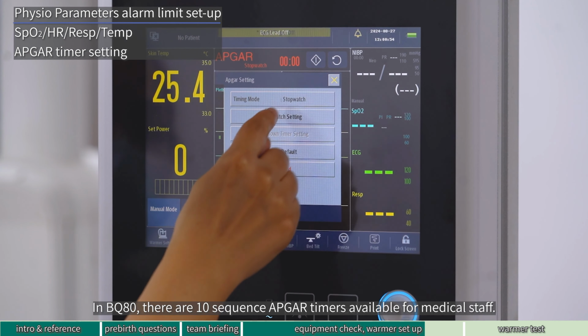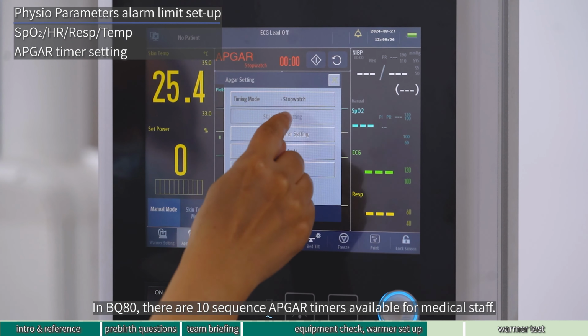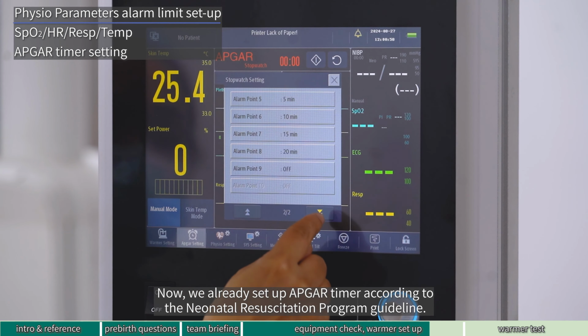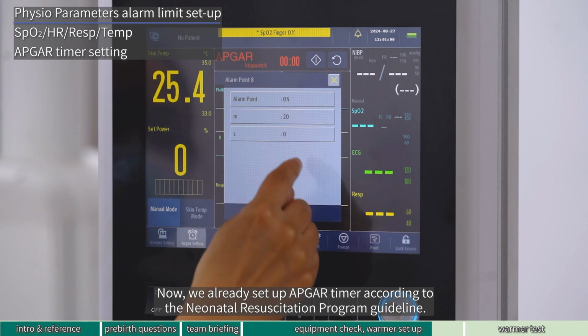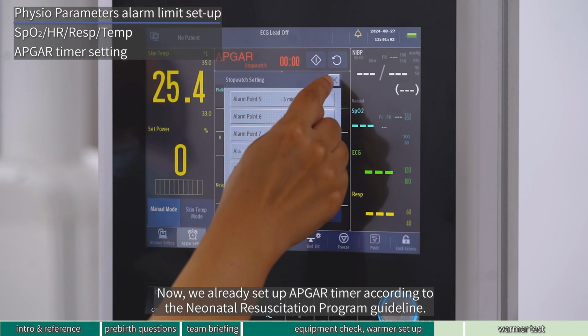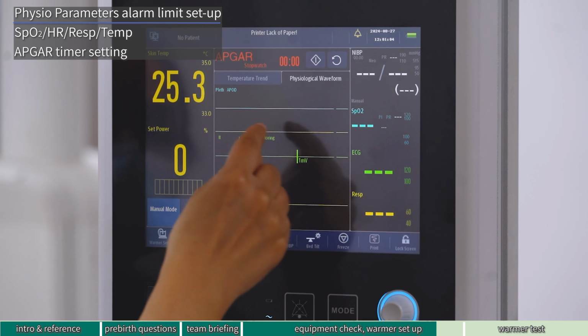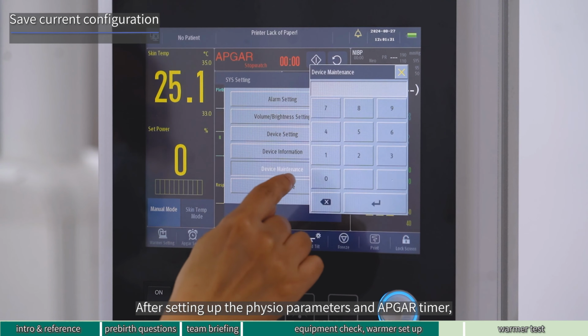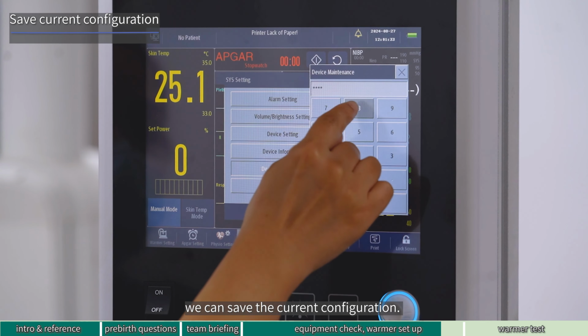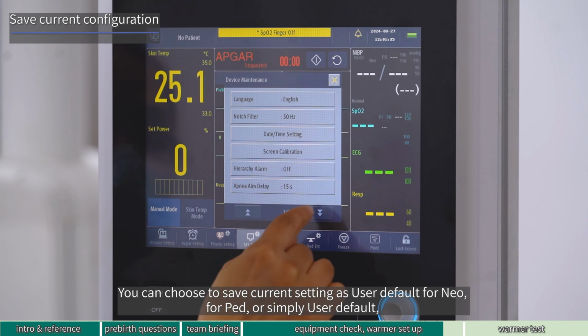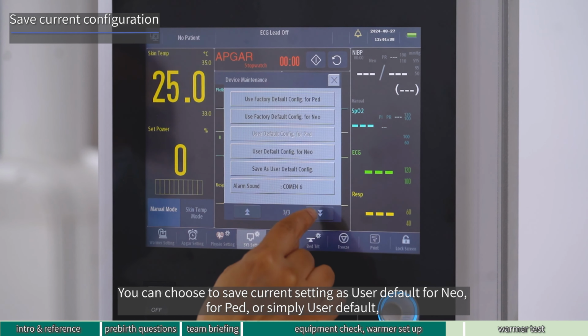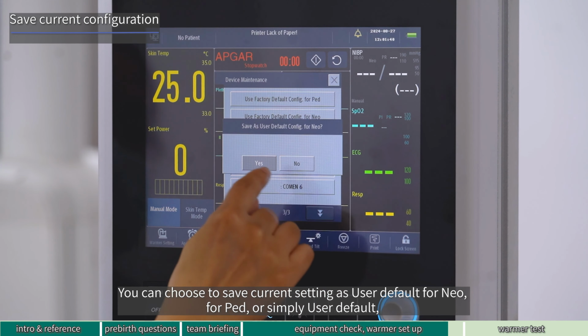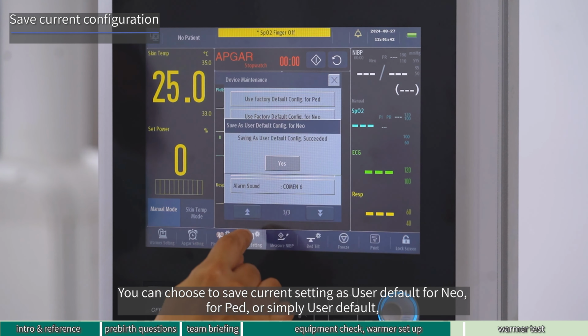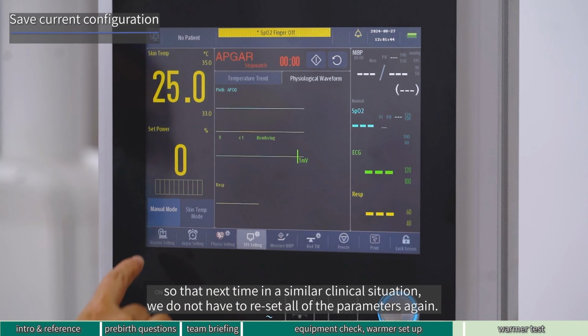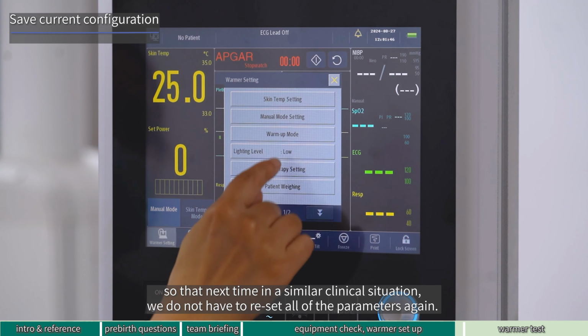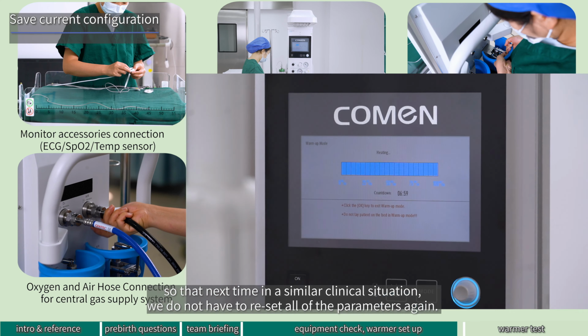In BQ80, there are 10 sequence APGAR timers available for medical staff. Now, we already set up APGAR timer according to the Neonatal Resuscitation Program guideline. After setting up the physio parameters and APGAR timer, we can save the current configuration. You can choose to save current setting as user default for Neo, for PED, or simply user default, so that next time in a similar clinical situation, we do not have to reset all of the parameters again.